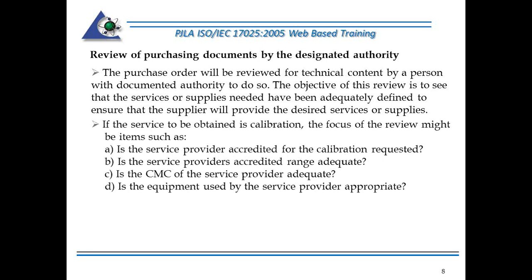If the service to be obtained is calibration, the focus of this review might be items such as, is the service provider accredited for the calibration requested? Obviously, you can't use them for an accredited calibration if this is either not on their scope or if it exceeds the ranges on their scope for which they're accredited. Is the service provider's accredited range adequate? Is the CMC of the service provider adequate?